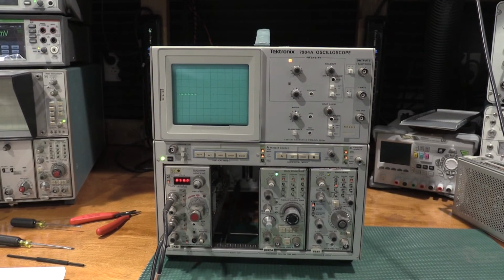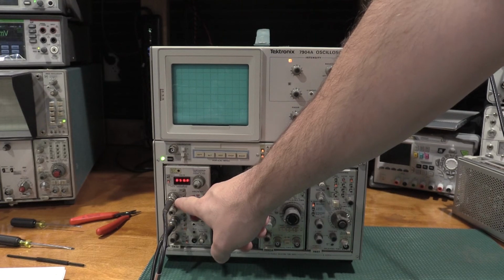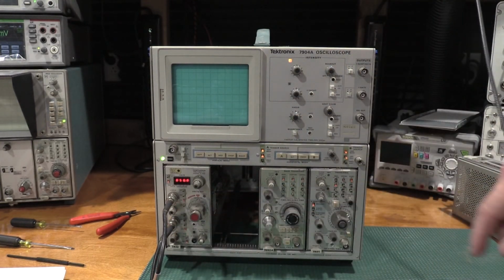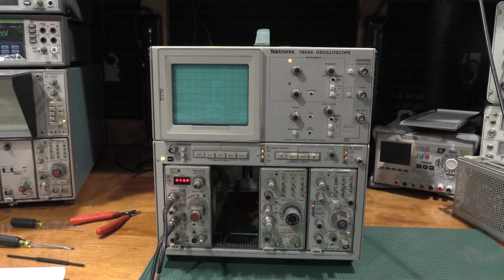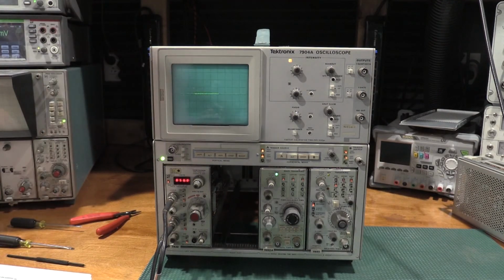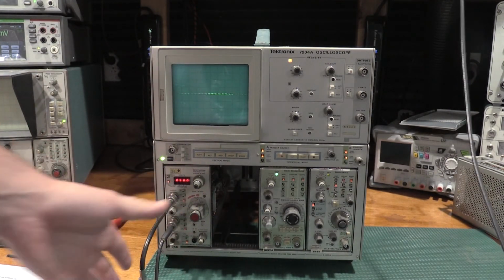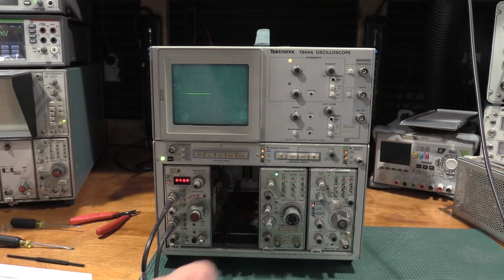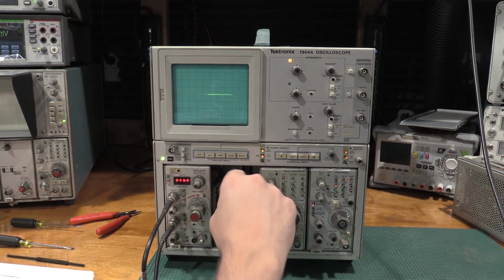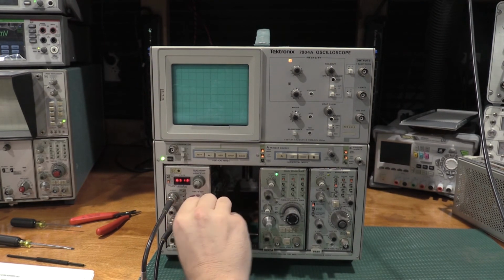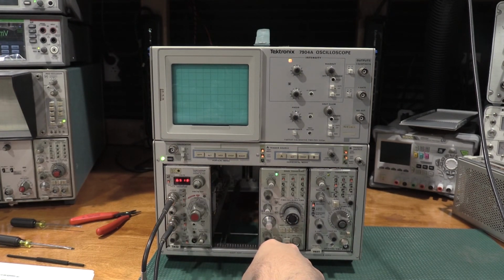Okay, this next one's a little confusing to set up. So we move over to the 106 again, and you set VC to negative 50. Plus input is DC, minus input is VC, and this is 050.0, and then we increase the amplitude of the 106 till it comes to graticule center. So as you're setting this up, there's nothing on the scope, nothing showing up, and then all of a sudden you get signal. So that's the setup for the controls, and we're still using the CMRR test cable. So then we need to do negative input mode to DC, and 0.1 volts. Two milliseconds.